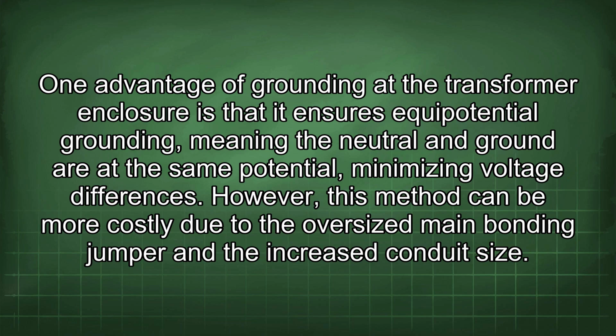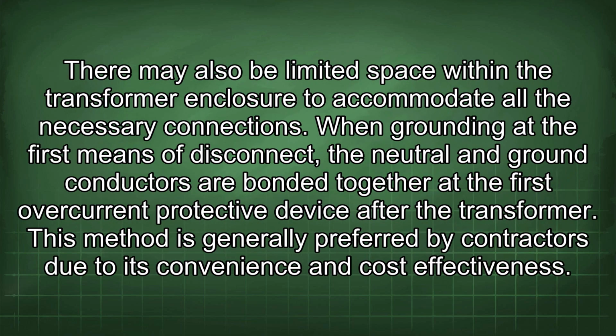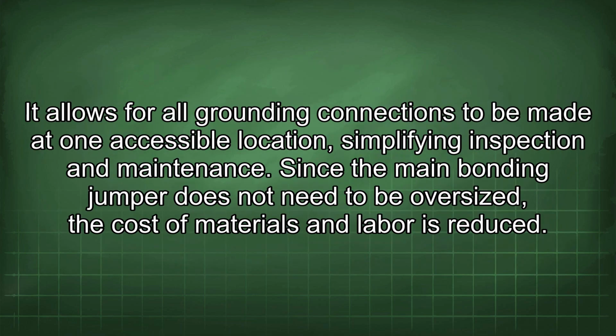However, this method can be more costly due to the oversized main bonding jumper and the increased conduit size. There may also be limited space within the transformer enclosure to accommodate all the necessary connections. When grounding at the first means of disconnect, the neutral and ground conductors are bonded together at the first overcurrent protective device after the transformer. This method is generally preferred by contractors due to its convenience and cost-effectiveness. It allows for all grounding connections to be made at one accessible location, simplifying inspection and maintenance. Since the main bonding jumper does not need to be oversized, the cost of materials and labor is reduced.